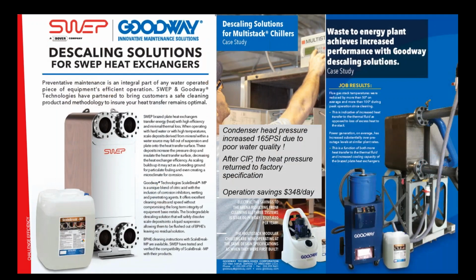And then of course the question would be, yes, but you cannot open a brazed plate heat exchanger. What if fouling happened, right? What we have seen is that cleaning in place has taken big strides during the lifetime of SWEP. Now cleaning in place is able to not only match but outmatch the possibility for mechanical cleaning. And I mean outmatch in an economic sense.